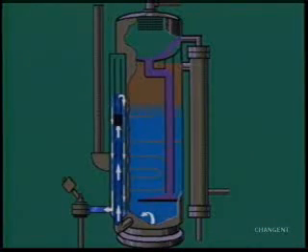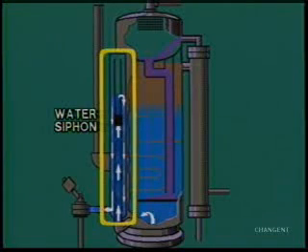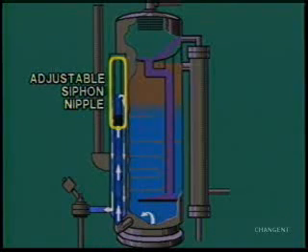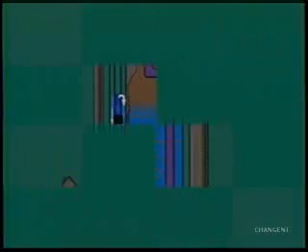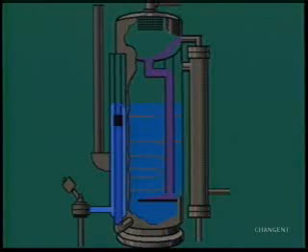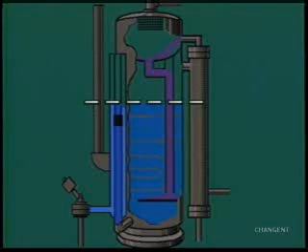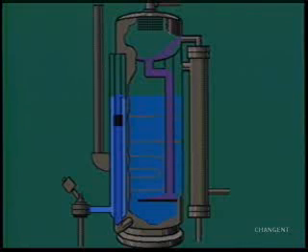The siphon system maintains the water level in the vessel. Water in the free water knockout section rises into the water siphon and flows over the adjustable siphon nipple, then leaves the unit through the water dump valve. Since water seeks its own level, the water level on the water siphon will be equal to the water level inside the treater. By changing the position of the siphon leg or nipple, the water level can be changed to maintain the oil-water interface.